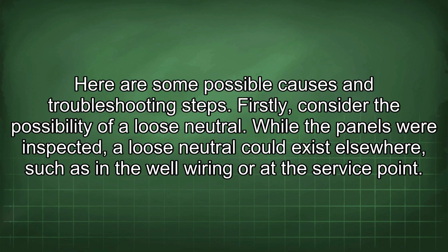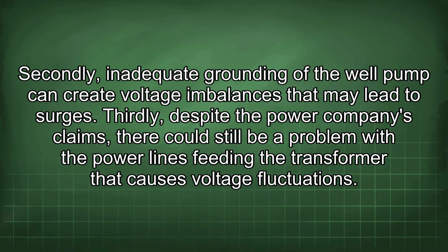Firstly, consider the possibility of a loose neutral. While the panels were inspected, a loose neutral could exist elsewhere, such as in the well wiring or at the service point. Secondly, inadequate grounding of the well pump can create voltage imbalances that may lead to surges.